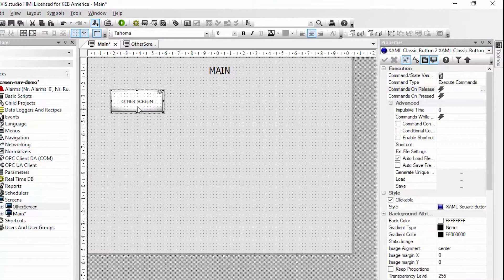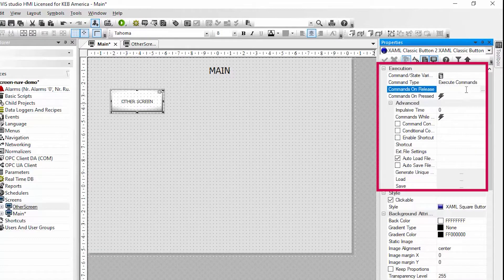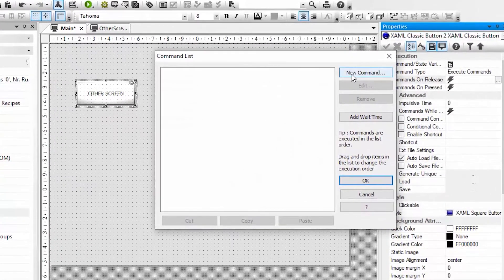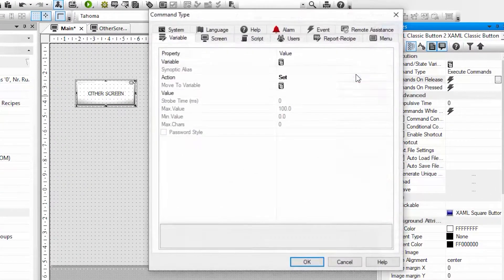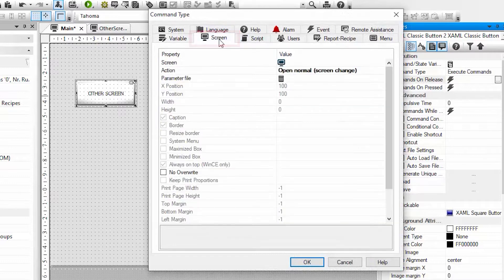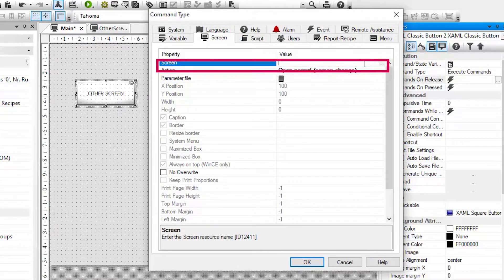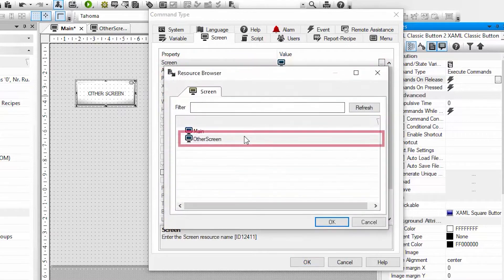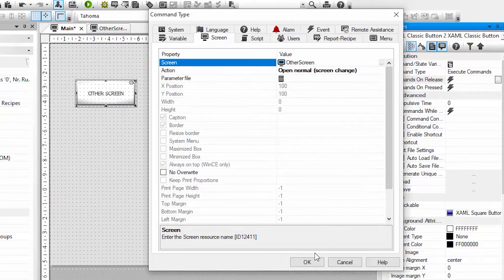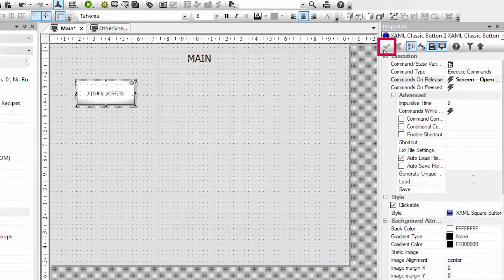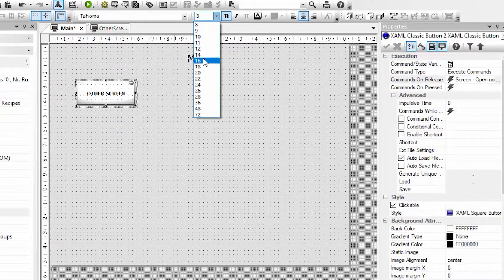The commands executed by the button are available here in the execution properties, and when I release the button I want to change screens. So I'm going to add a new command, select the screen command type, open normal screen change, and I will select my other screen. Click OK. I'm going to make this font a little bigger to see.